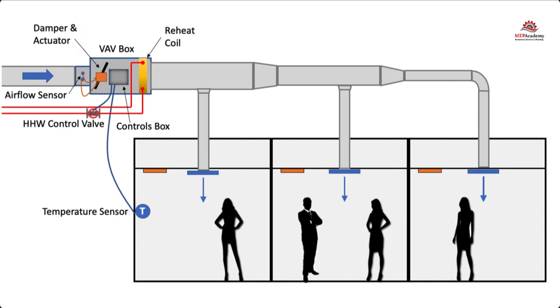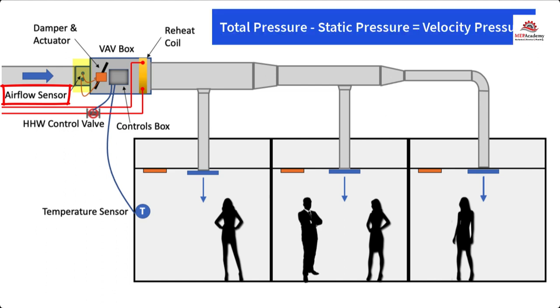There is an airflow sensor at the inlet of the box, and that is used to adjust the damper position by measuring the airflow at the inlet of the box. The airflow sensor measures total pressure and static pressure to determine the velocity pressure, which helps the controller determine the CFM through the inlet of the VAV box. Velocity pressure equals total pressure minus static pressure.